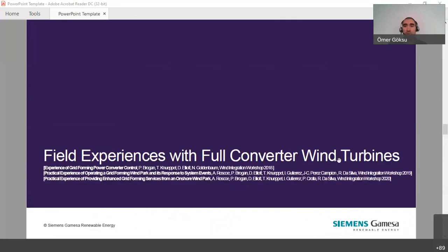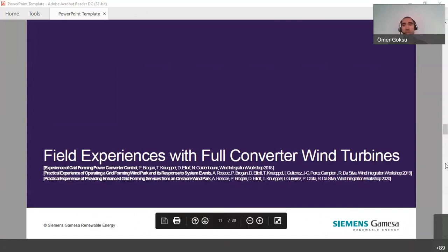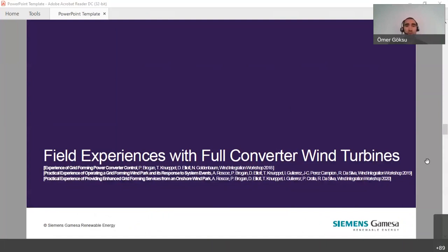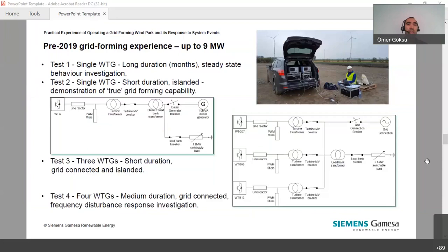So this is from three previous studies from 2018, 19, and 20. Some field results with full converter wind turbines with grid forming technology. Before 2019, it started with a single turbine running grid connected in the first test for long durations, to observe this behavior, its impact on the turbine and its production also. Some 5-6,000 megawatt hours of energy were produced during this duration.